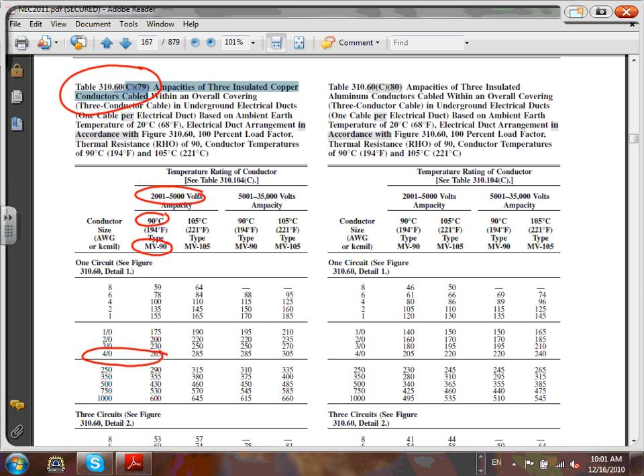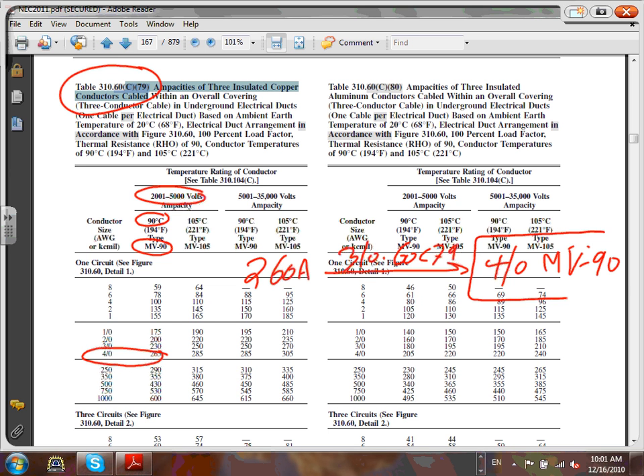Okay, I want to bring your attention to this, guys. My current was 260 amp. When you take it to this table, in my case 310.60, it will get you 4 aught. Next to the 4 aught, please write down what I'm going to write: medium voltage dash 90. And how many conductors? 3. Three conductors, 4 aught, medium voltage dash 90. MV, medium voltage 90. The insulation is rated for 90. That's unlike everything that we did in low voltage. We never size conductors based on 90. We always size at maximum 75. We derate based on 90, but we never size.